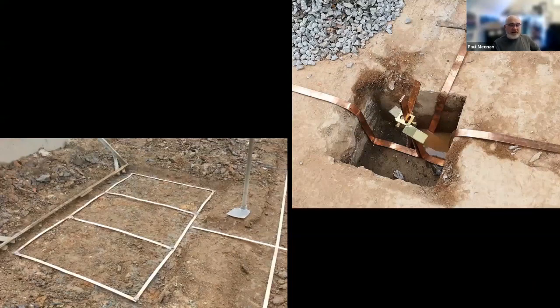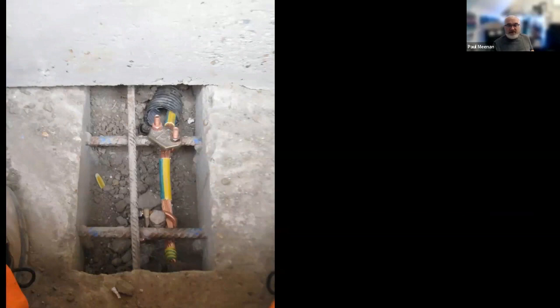Some good practices here in England. When we're building stuff, we use earth tapes, welded connections, and we create pits to create a large earth mat. They can also use rods as well. That gets covered up. We can also connect to rebar. So piling, that's a Crossrail transformer there. And what we did was we basically put 28-meter piles in the ground, 150 of them, and connected the earthing conductor to the pile cap. And we got a fantastically robust, low impedance earth. So you can use structures and you can use metalwork in the ground. You just make sure that you protect it from corrosion and you inspect it accordingly.